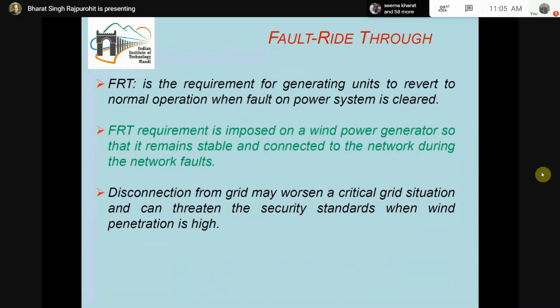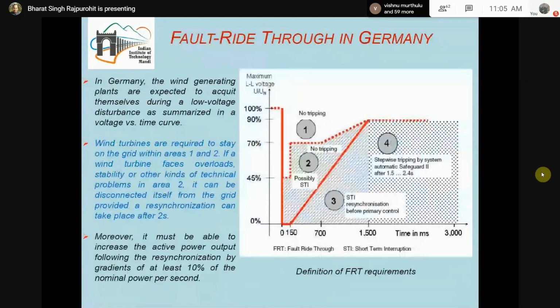The next requirement is known as fault ride through. Fault ride through is the requirement that the generator remains connected to the grid and is able to supply active and reactive power as per the grid requirement. They should not simply get disconnected from the grid during abnormal conditions. So this is the requirement. Now please see this figure. This is also from a German grid code.